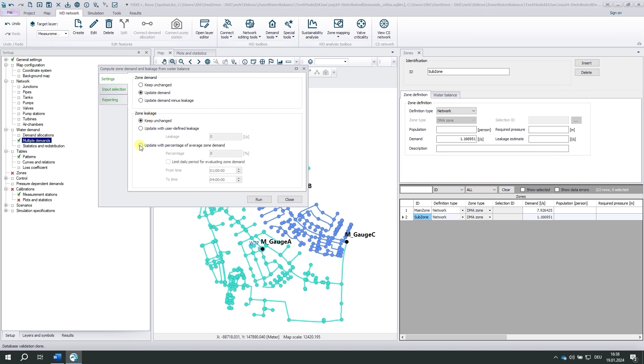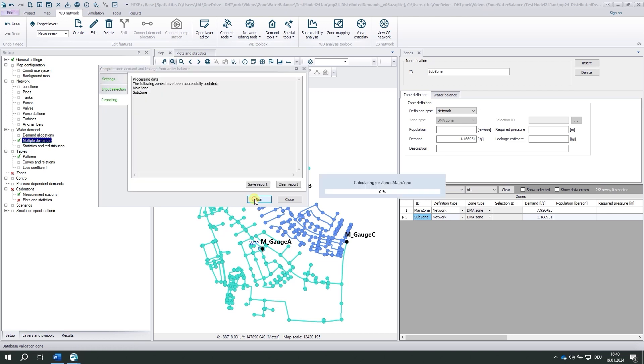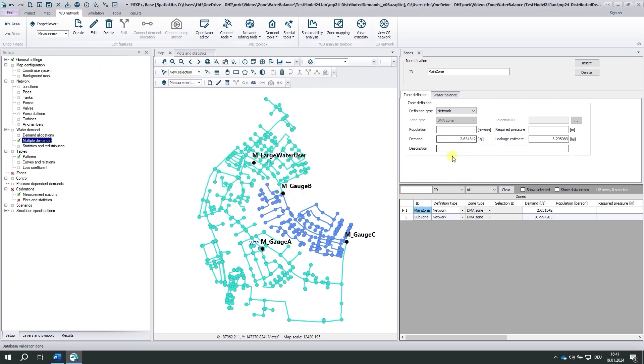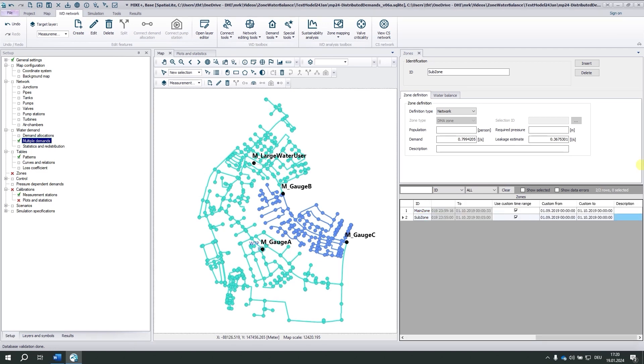Here, zone leakage. We would take the average between 11 o'clock in the evening and 4 o'clock in the morning and assume that this is the leakage. On the other hand, we will subtract this constant value from the demand we've just computed. We click run. And now the tool has populated leakage and demand both in the main zone and the subzone. This was the compute zone demand tool.